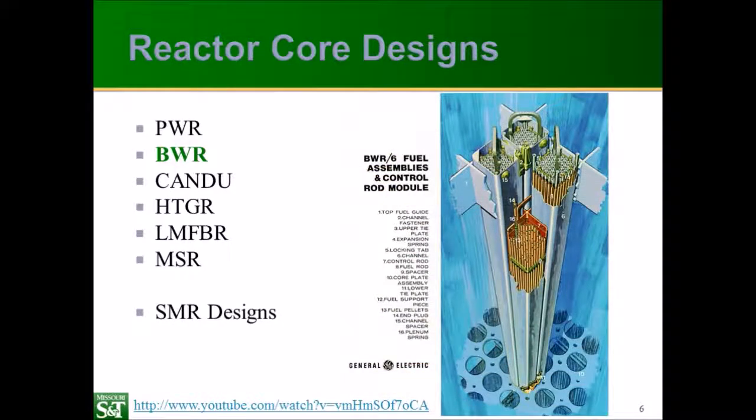The fuel here, you're going to have the heat generation in the core from the fission chain reaction, and the conduction and then convection. However, in a BWR, we use control blades, which are kind of shaped like an X rather than control rods. And these actually have to enter from the bottom of the reactor because the steam separators and other components are above the reactor and the control rods can't move through those.